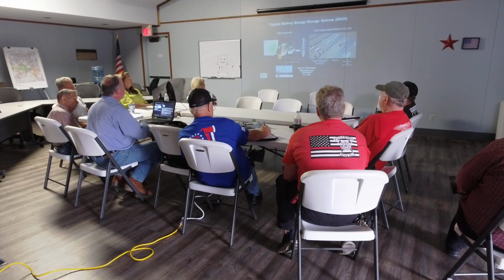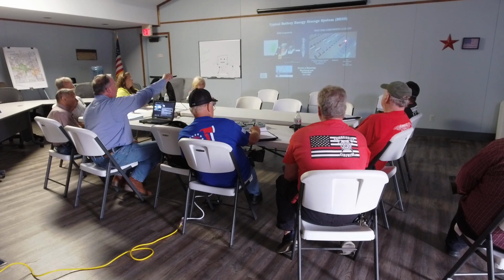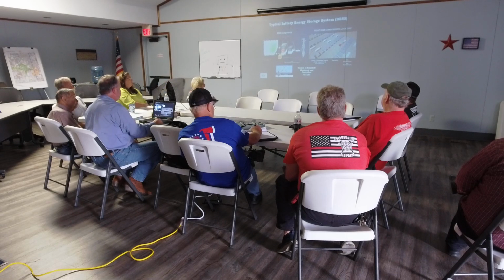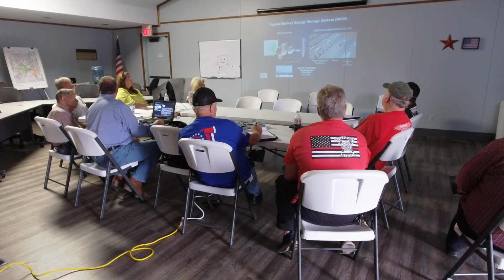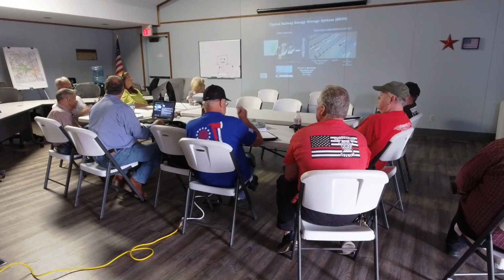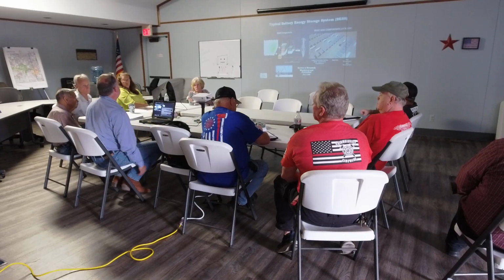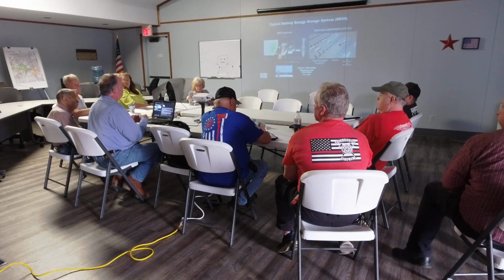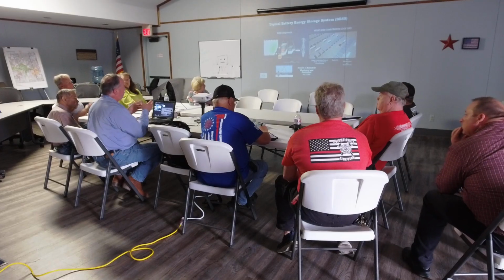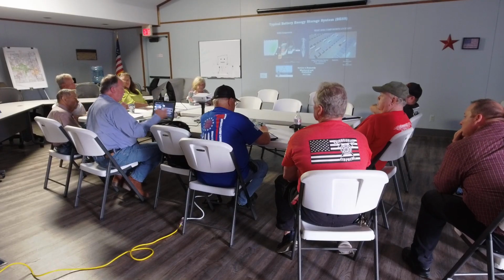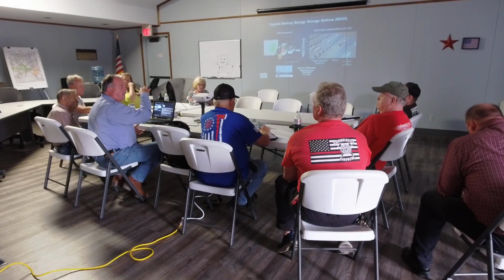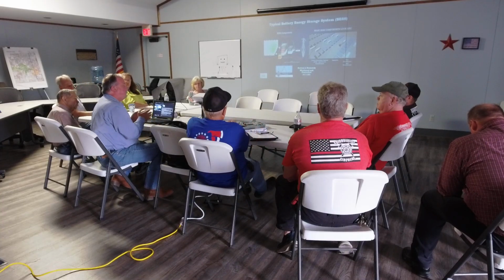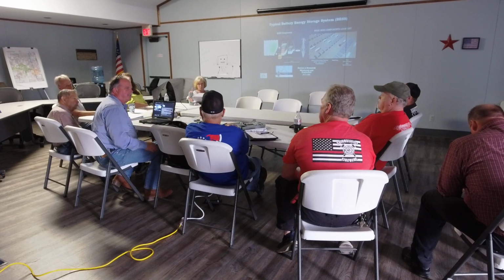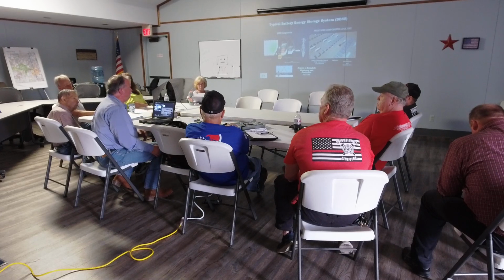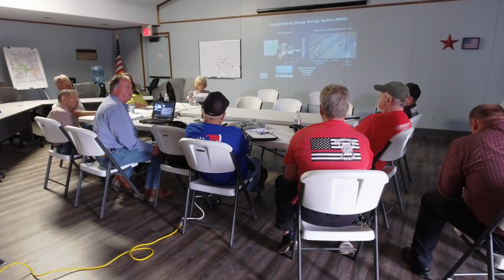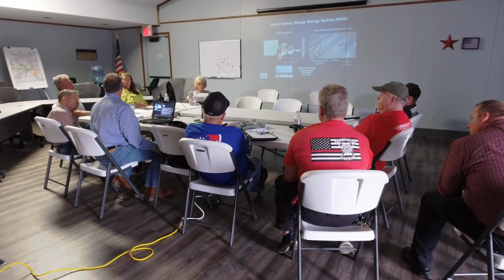By the time they put in all the other ancillary equipment, like auxiliary transformers to run the blowers and ventilation systems, there's a maximum size for the battery storage units too. The battery units themselves—think of a shipping container, though they're not shipping containers anymore, they're purpose designed—are 20 feet long, typically 8.5 by 9.5. The reason we're not likely to see them get larger individually is the weight. The battery containers weigh upwards of 110 to 120,000 pounds each, so logistics becomes an issue.